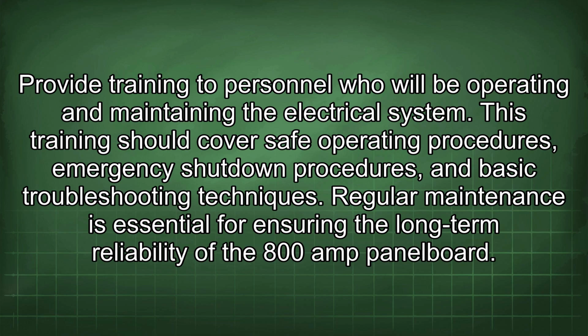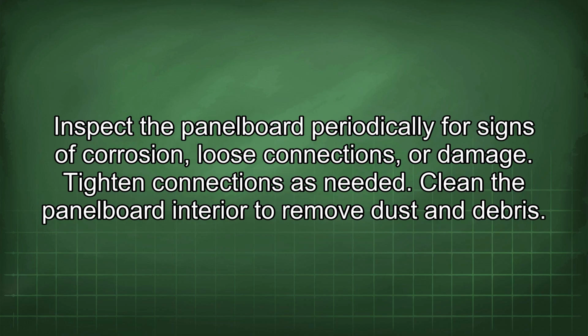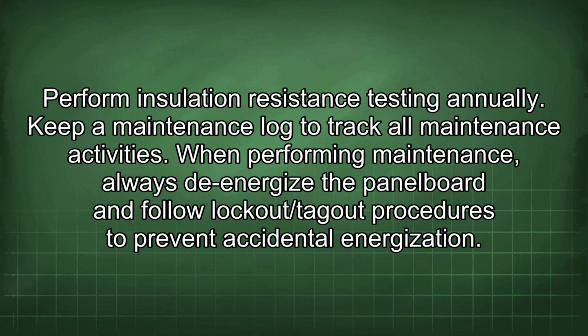Regular maintenance is essential for ensuring the long-term reliability of the 800 amp panel board. Inspect the panel board periodically for signs of corrosion, loose connections, or damage. Tighten connections as needed. Clean the panel board interior to remove dust and debris. Perform insulation resistance testing annually. Keep a maintenance log to track all maintenance activities.